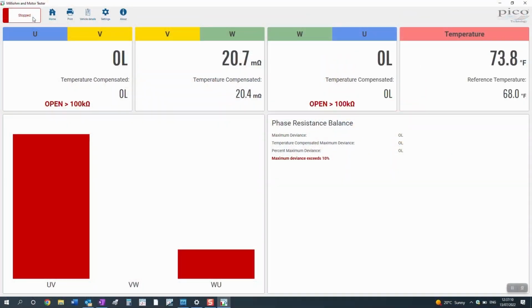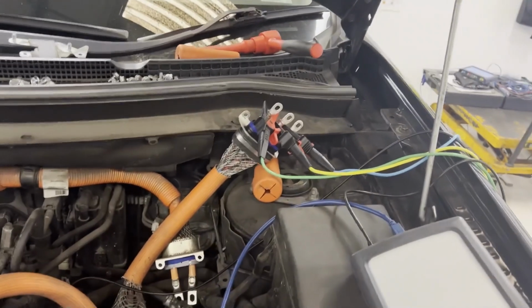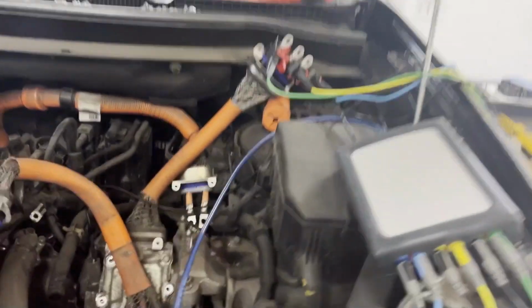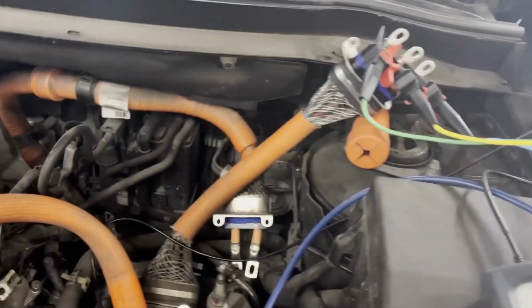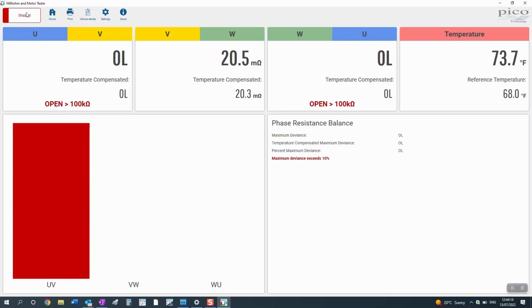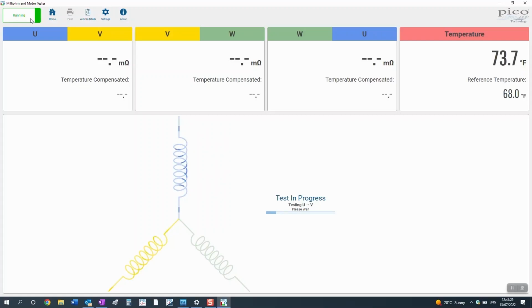And as we can see here, a number of issues already. Between U and V, let us just actually see what happens when we take the U phase down to ground. Let's find out how that has changed. Now we're going to measure phase V to U, but U is actually now at ground. So let's see how this has changed. Yeah, that kind of reinforces this concern we have that we'd spotted with the isolation test, the insulation test. We do have a short to ground.